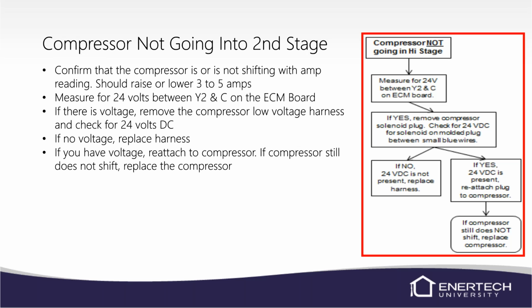There's a rectifier inside that little black molded plug, and it switches it from AC to DC volts. If you have AC voltage at the ECM board, but you don't have it out of the plug, then the plug is bad and it'll have to be replaced. At least in that situation, the compressor will still run in first stage. It's not the end of the world. At least they'll get some cooling. They may not be able to keep up, but at least they'll have some cooling for them.